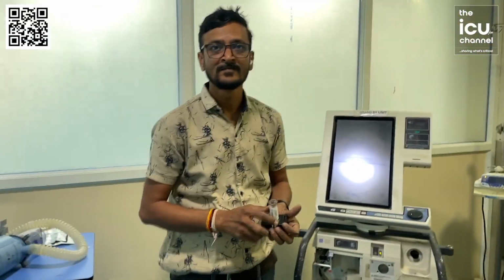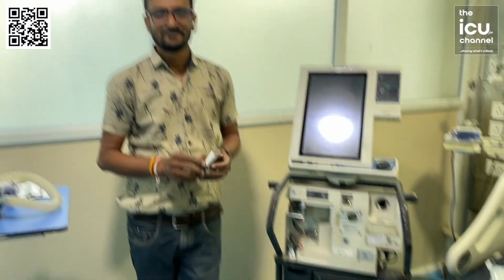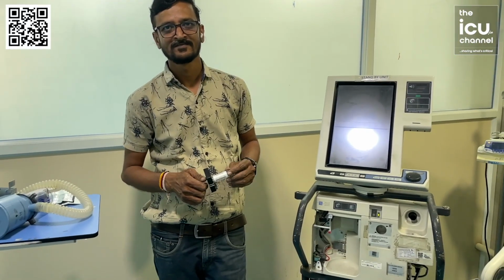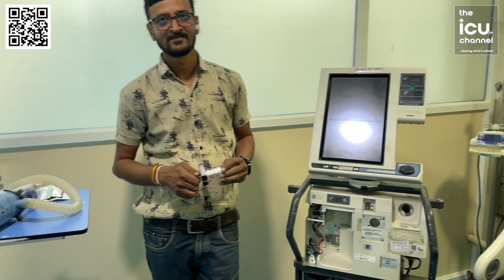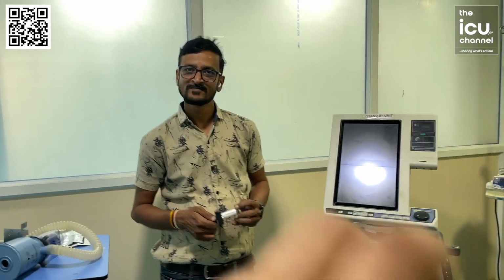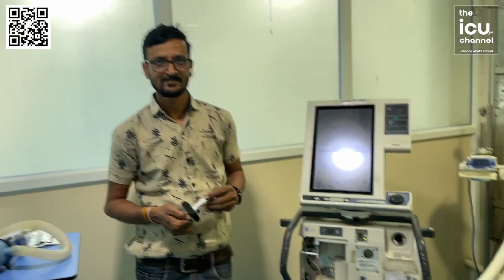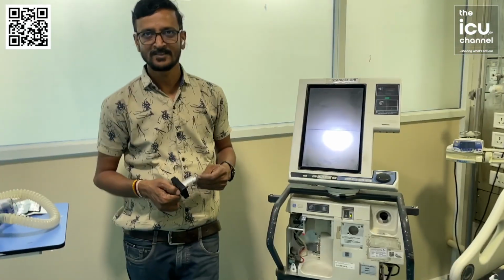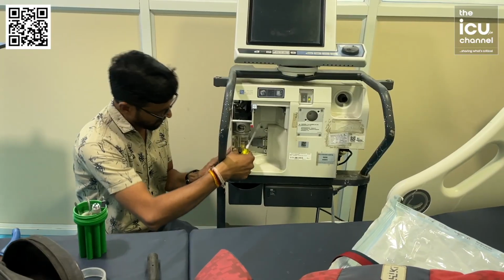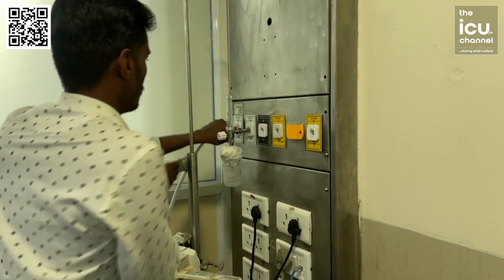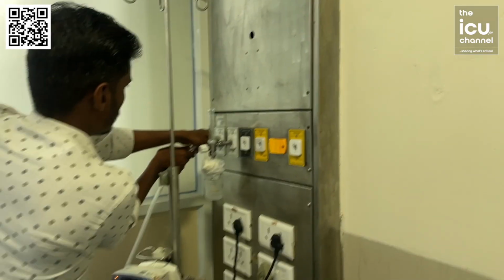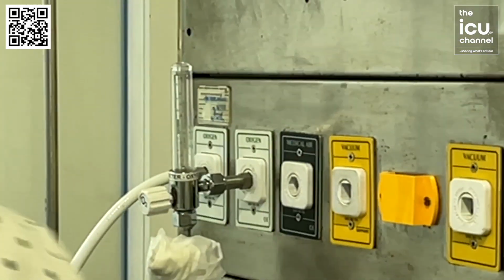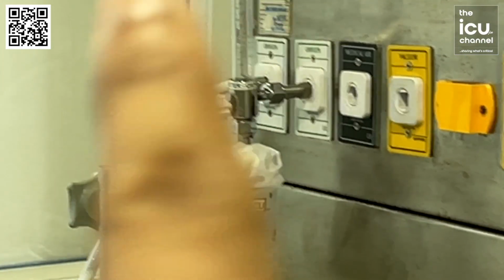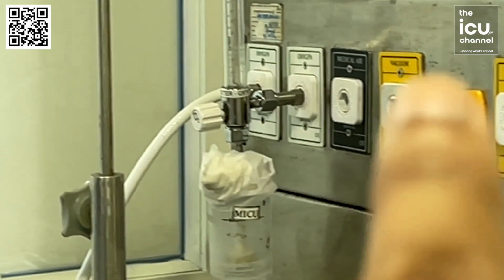Let Praveen check all the valves and all those things. And once we are set with this, we'll tell you how to use this information in interpreting the graphs and the values which are coming on the ventilator screen. Okay. Pawan is now closing the expiratory limb. So now we are connecting one to the oxygen port. This is the oxygen port, and this is the air. Black one is the air.